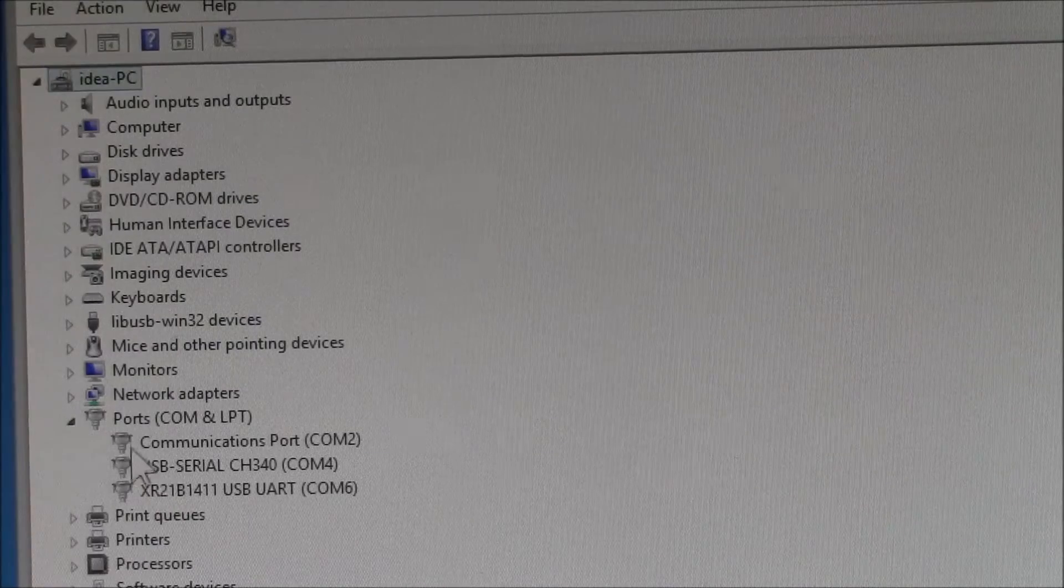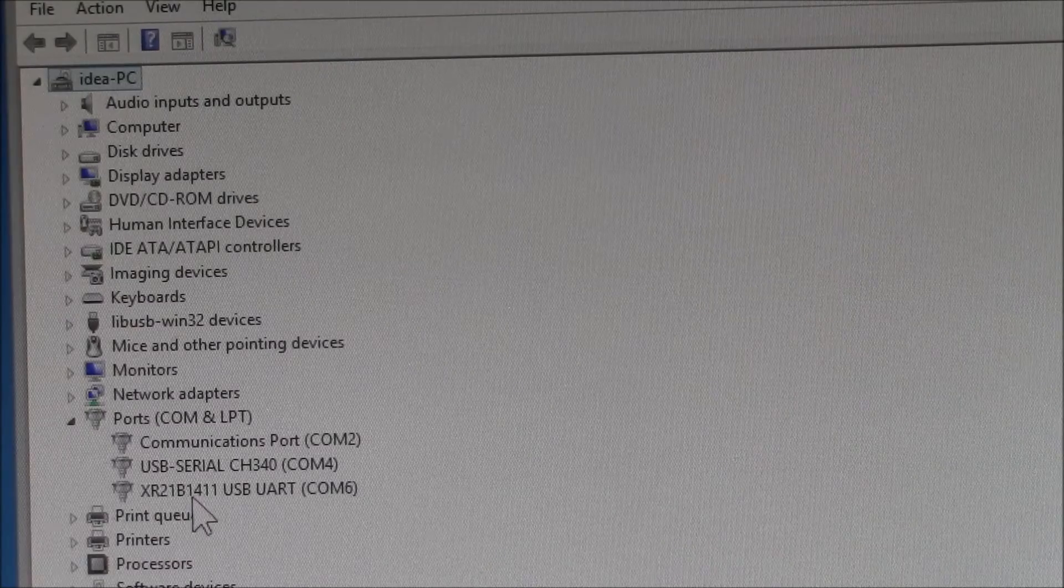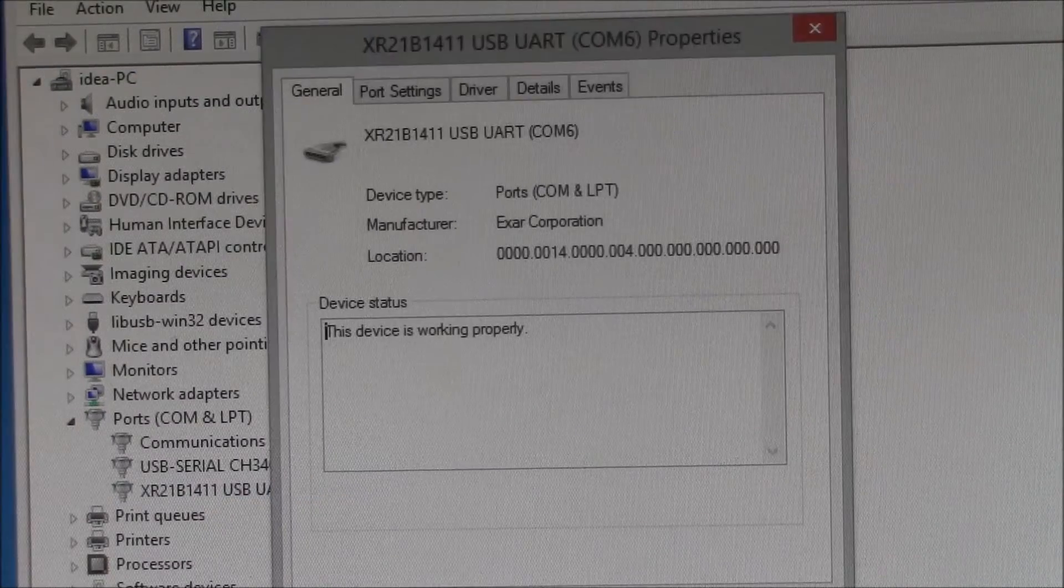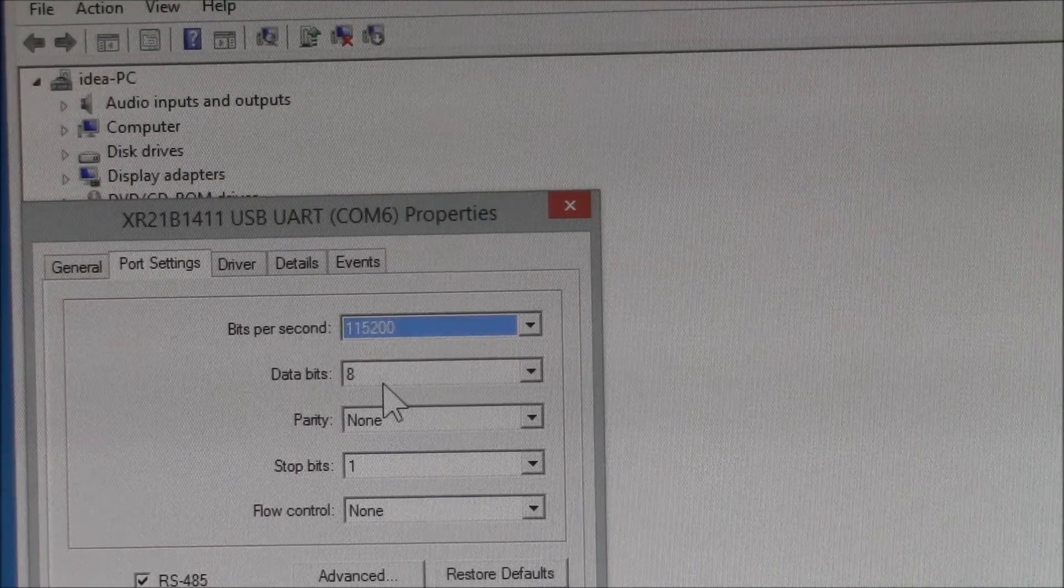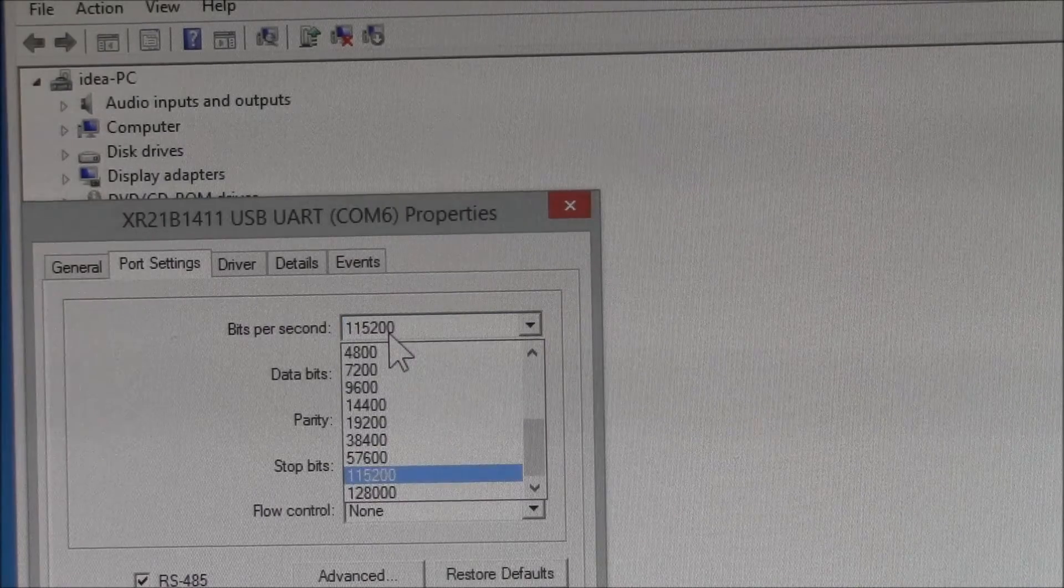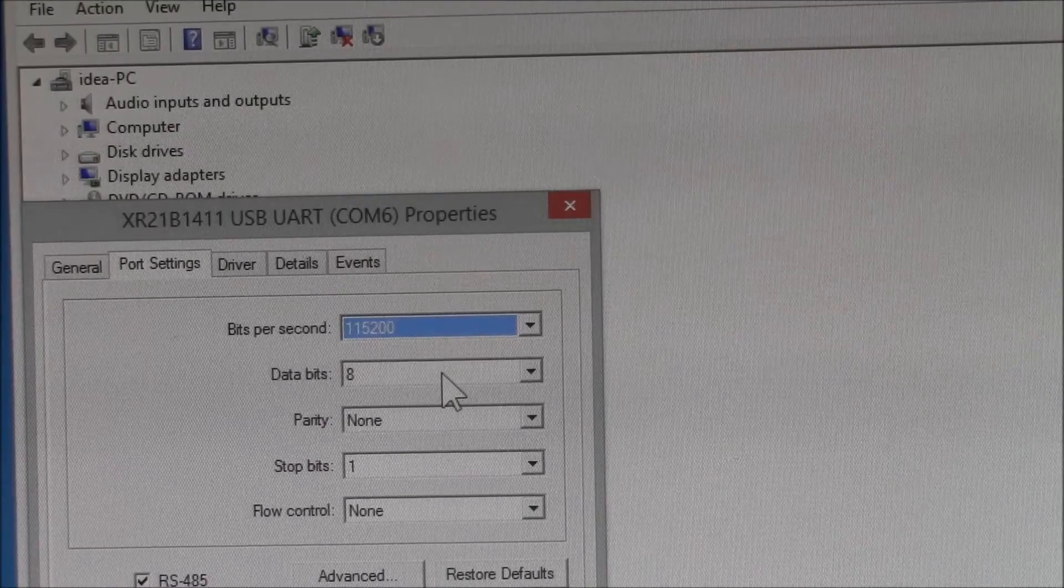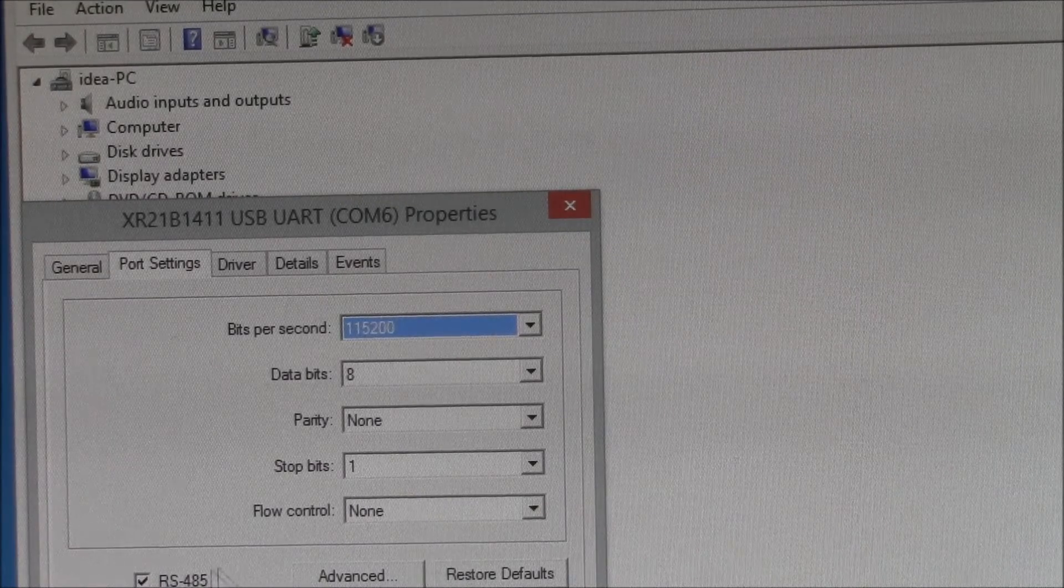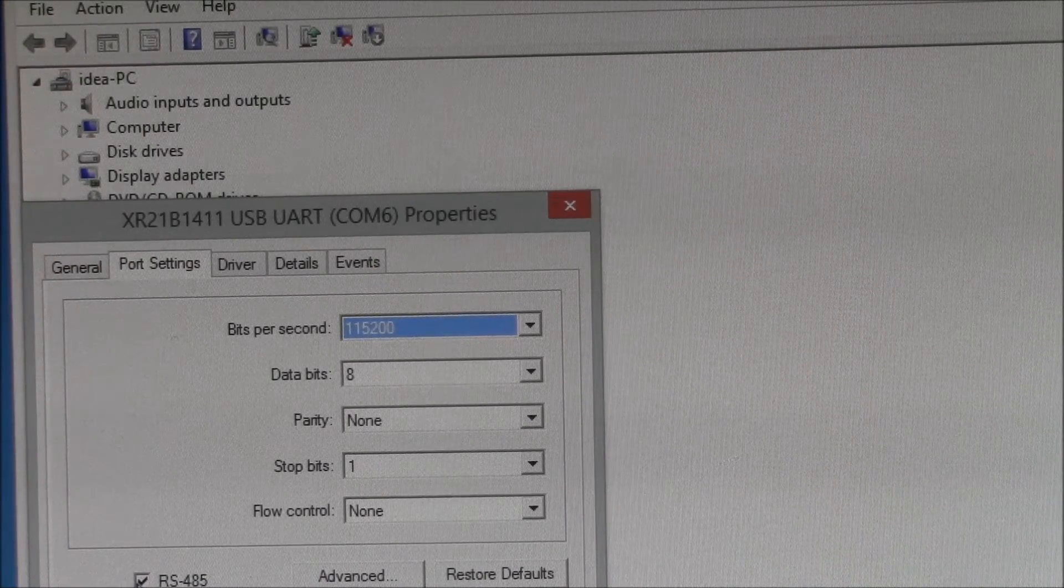What you want to do is come down here to your ports. That device is called an XR21B1411. Double click on that and that brings up the device properties. Come over here to port. You need to set the bits per second to 115,200, eight bit data, no parity, one stop bit, and no flow control. Then you need to check that box right there, RS-485. You need to get that enabled because that's the communications mode.